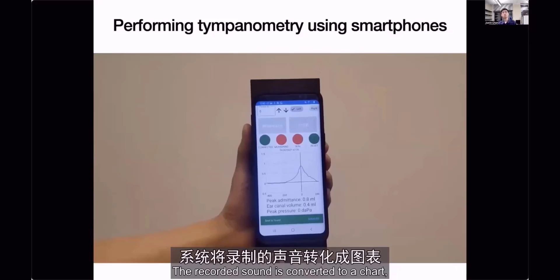Okay, so let's take a look at what's at the heart of this device. Right on the inside is a pressure transducer, and that's used to actually change the amount of pressure within the ear canal. So it pushes the eardrum forward and it moves it backwards as it introduces more and takes away a little bit of pressure to the eardrum. So a commercial tympanometer typically uses a pretty expensive setup for this, but we asked what's the cheapest pressure transducer that you can go to. And as it turns out, we designed just a very cheap transducer just using a cheap syringe that just costs less than $1 to change the pressure within the ear.